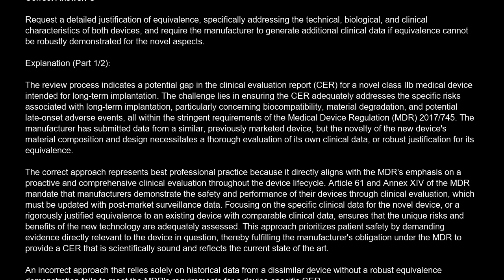The correct approach represents best professional practice because it directly aligns with the MDR's emphasis on a proactive and comprehensive clinical evaluation throughout the device lifecycle. Article 61 and Annex XIV of the MDR mandate that manufacturers demonstrate the safety and performance of their devices through clinical evaluation, which must be updated with post-market surveillance data. Focusing on the specific clinical data for the novel device, or a rigorously justified equivalence to an existing device with comparable clinical data, ensures that the unique risks and benefits of the new technology are adequately assessed. This approach prioritizes patient safety by demanding evidence directly relevant to the device in question, thereby fulfilling the manufacturer's obligation under the MDR to provide a CER that is scientifically sound and reflects the current state of the art.